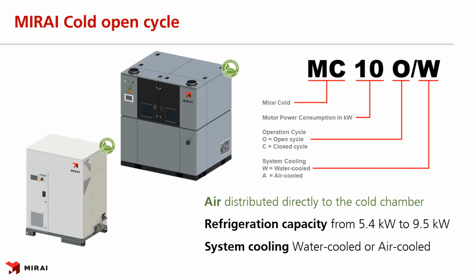There are two basic principles how Mirai Cold works, in open and closed cycle. I'll explain our nomenclature for open cycle machine first. MC stands for Mirai Cold. The number behind represents motor power consumption in kilowatts. O stands for open cycle. And the last letter represents means of system cooling, so either water or air.